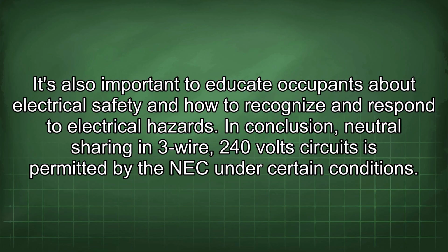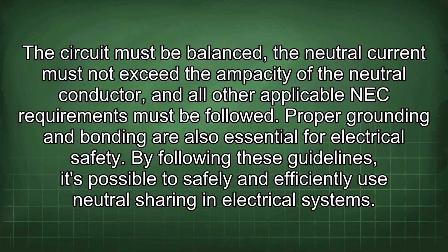In conclusion, neutral sharing in 3-wire 240-volt circuits is permitted by the NEC under certain conditions. The circuit must be balanced, the neutral current must not exceed the ampacity of the neutral conductor, and all other applicable NEC requirements must be followed. Proper grounding and bonding are also essential for electrical safety. By following these guidelines, it's possible to safely and efficiently use neutral sharing in electrical systems.